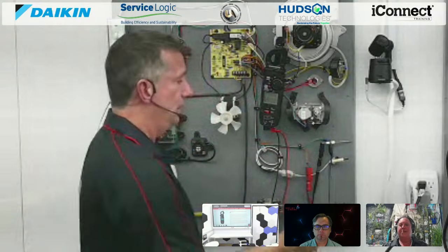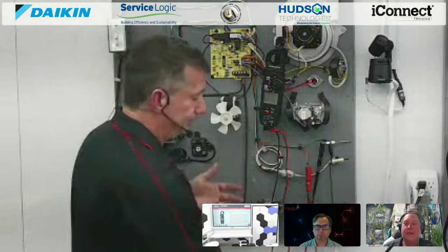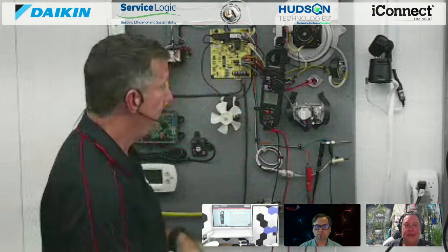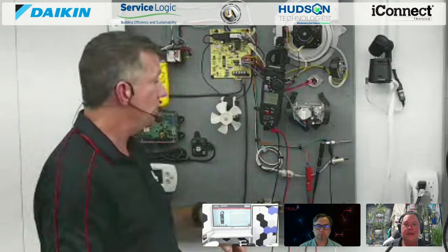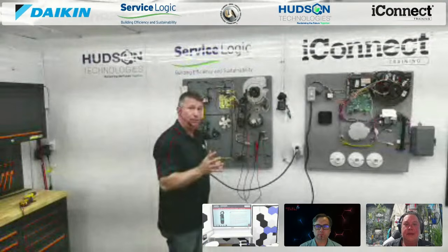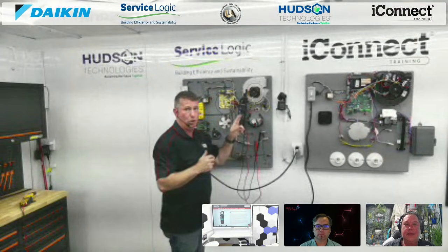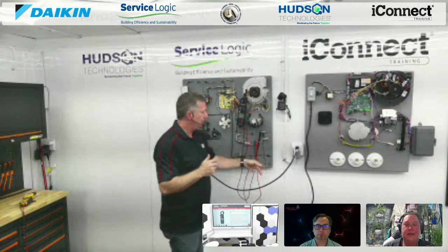of amperage. And so if we think about the sequence of operation, let's go through that, right? Sequence of operation: the thermostat is going to come on. It's going to start our draft inducer. After a period of time, we're going to bring on our hot surface igniter. After our igniter gets to temperature, we're going to open up our gas valve. And then we're going to be looking for our load with our flame sensor.